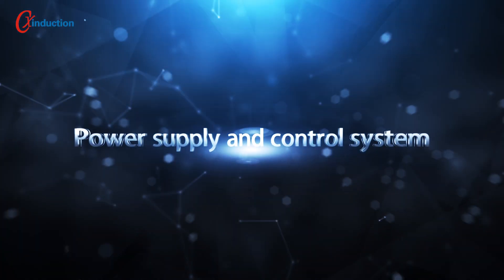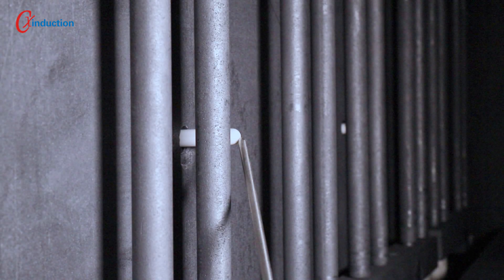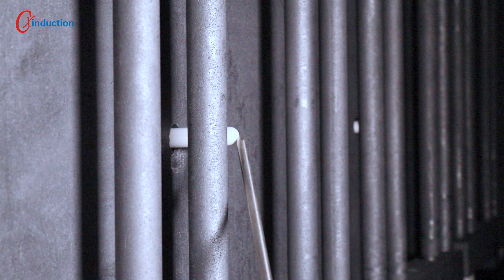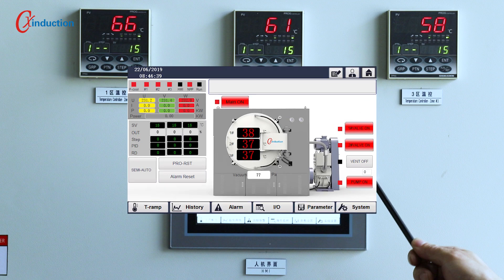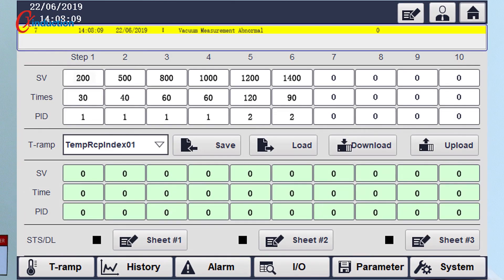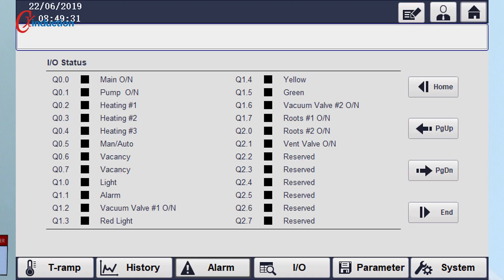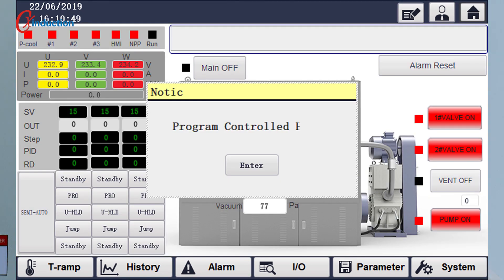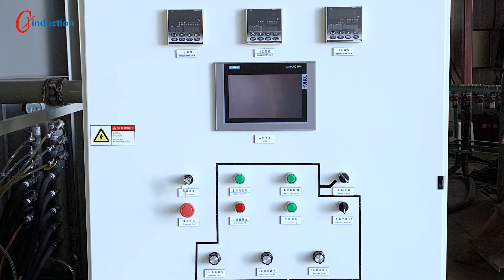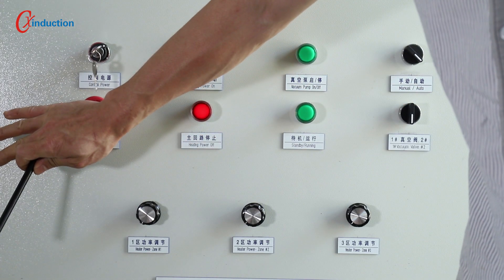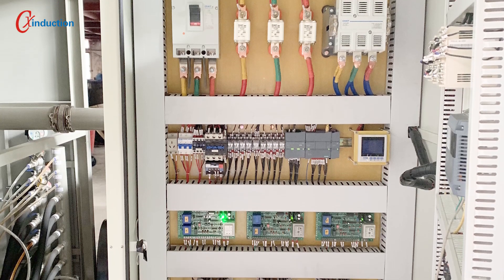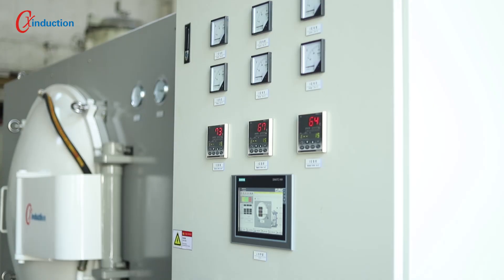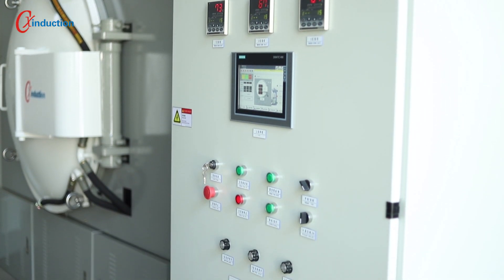Three: power supply and control system. Tungsten rhenium thermocouples are installed in the middle of the left side of each group of heating elements for temperature measurement. The reasonable setting of the temperature control instrument data on the touch screen can control the temperature within ±1°C. Most operating functions can be done on the touch screen, and the touch screen records running data for the user to analyze. On the panel of the cabinet, the manual control function is retained and the emergency stop function is used in emergency situations. The control system is installed inside the cabinet and non-professionals are not allowed to open it. All running status of the carbonization furnace is displayed on the panel of the cabinet.